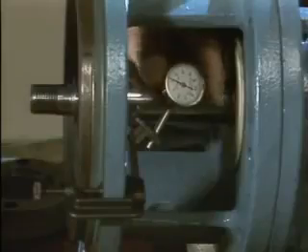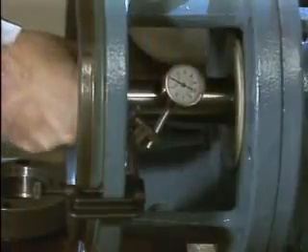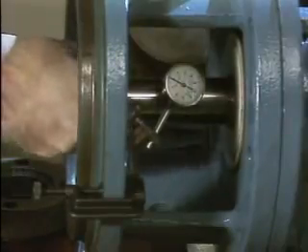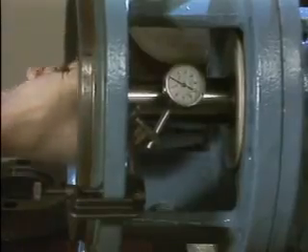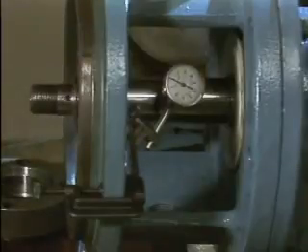There are other important checks that should be made before a mechanical seal is installed. Some of these checks involve the use of dial indicators. One important check is testing for shaft runout. A shaft that's bent or out of round can damage pump components and prevent a mechanical seal from operating properly. Before the measurement is taken, the dial indicator is zeroed. Then the shaft is rotated. The dial indicator should measure any shaft runout that's present. To determine if the runout is excessive, you'll need to refer to your company's policies and procedures or to the pump manufacturer's specifications.